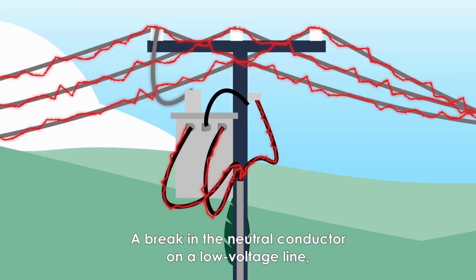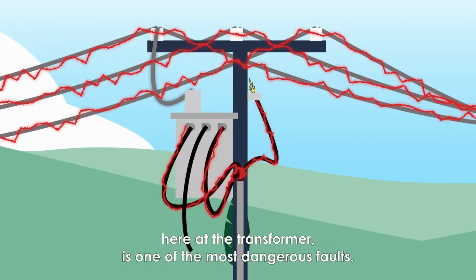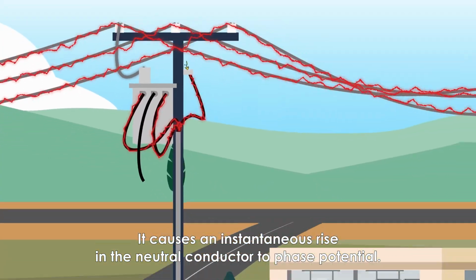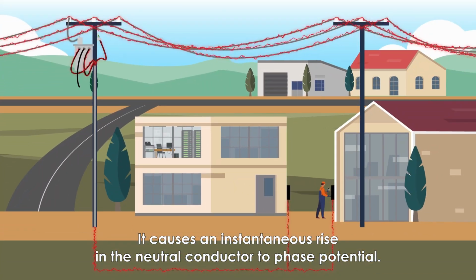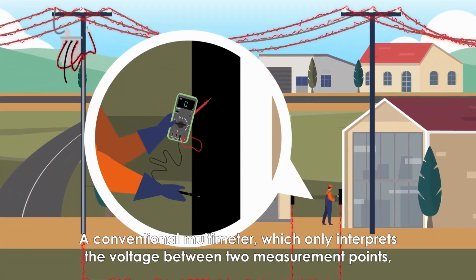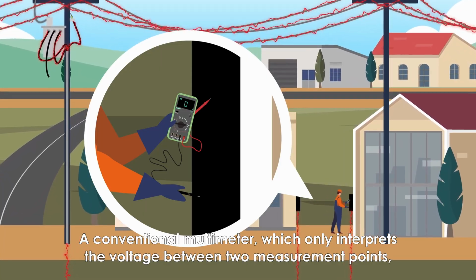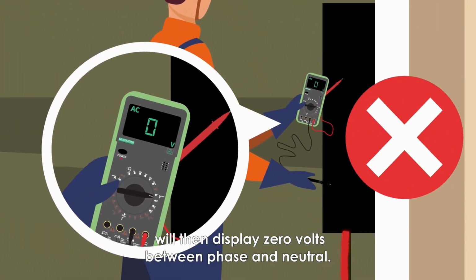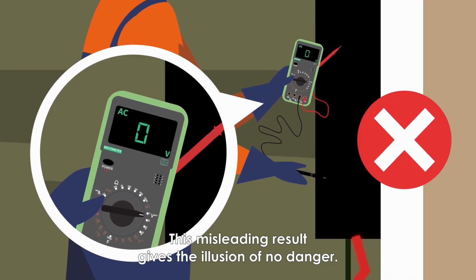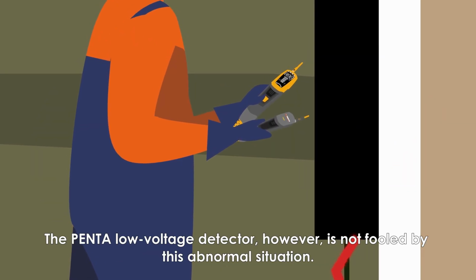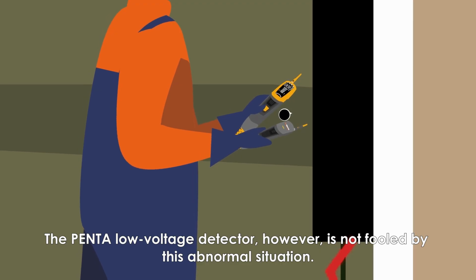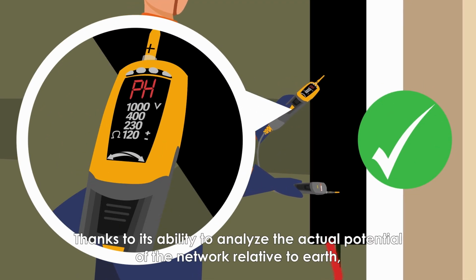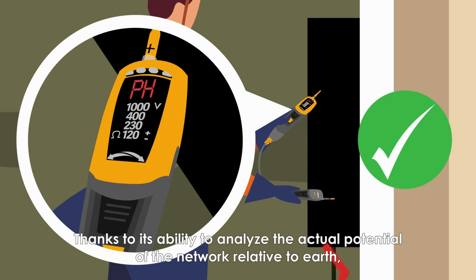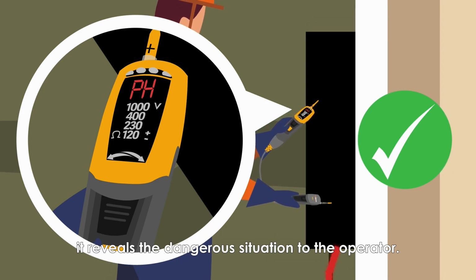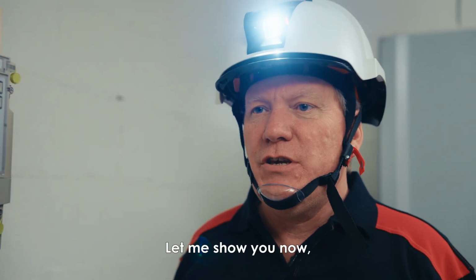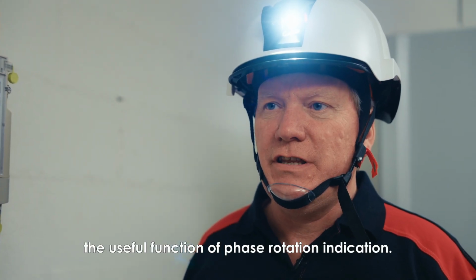A break in the neutral conductor on a low voltage line, here at the transformer, is one of the most dangerous faults. It causes an instantaneous rise in the neutral conductor to phase potential. A conventional multimeter, which only interprets the voltage between two measurement points, will then display 0 volts between phase and neutral. This misleading result gives the illusion of no danger. The Penta low voltage detector, however, is not fooled by this abnormal situation. Thanks to its ability to analyze the actual potential of the network relative to Earth, it reveals the dangerous situation to the operator. Let me show you now the useful function of phase rotation indication.